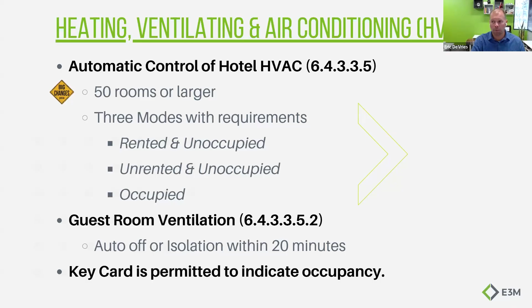This is something, right? And what gets interesting with this is this is a pinch point, or a pivotal point that we've heard from other states. If you're going design build, or if you're a mechanical contractor, you really need to be coordinating with the electrical contractor now, because different things might signal occupancy. There might be a lighting occupancy sensor that signals that the room is occupied. There's got to be a collaboration and a communication that occurs from a requirement like this.